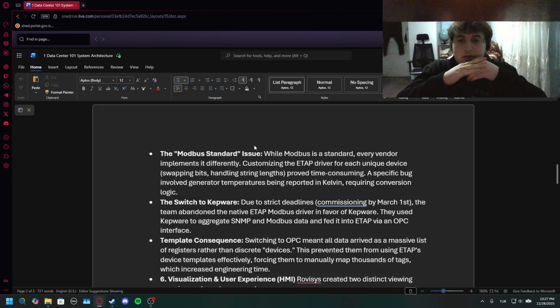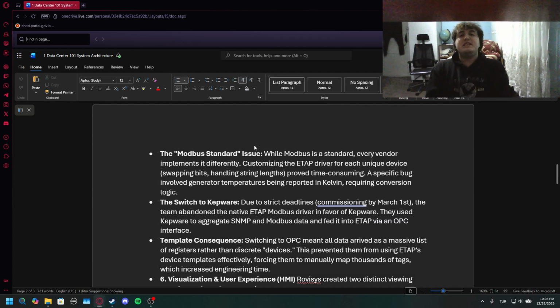They used Kepware to aggregate SNMP and Modbus data, feeding it into ETAP via an OPC interface. Here's the deal - the deadline forced them to change the native ETAP Modbus driver. You could do this, but will it be good? Will it be useful? Will it cause a problem? All of these changes mean you cannot just instantly change something - you need to think about all the other factors, and when you're on such a short timeline, sometimes you just don't.